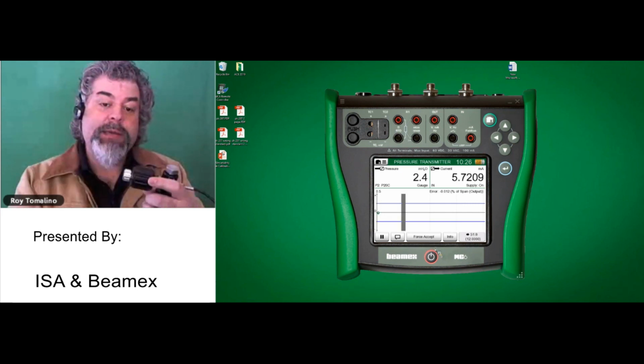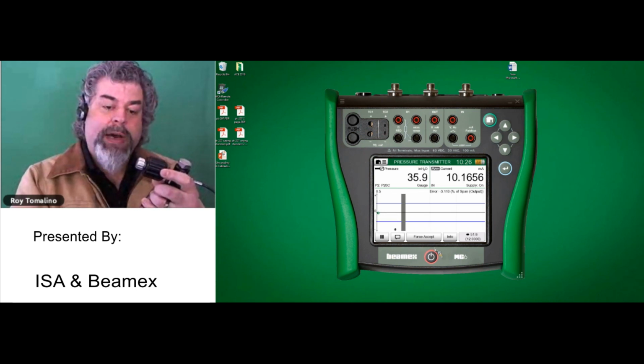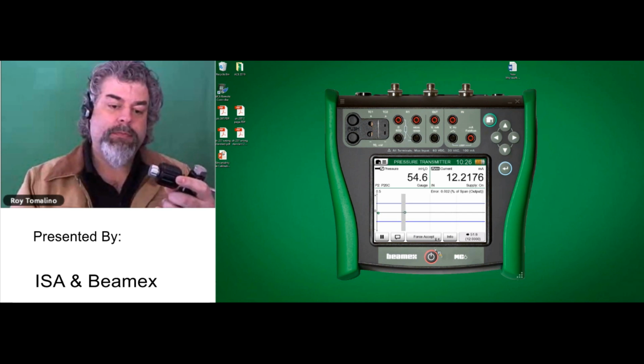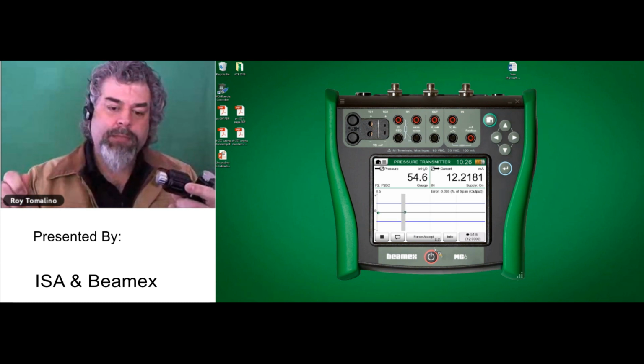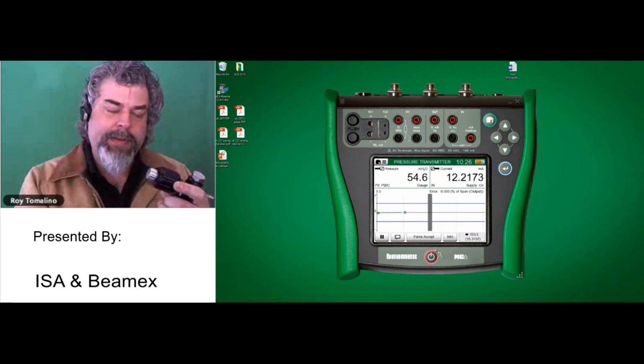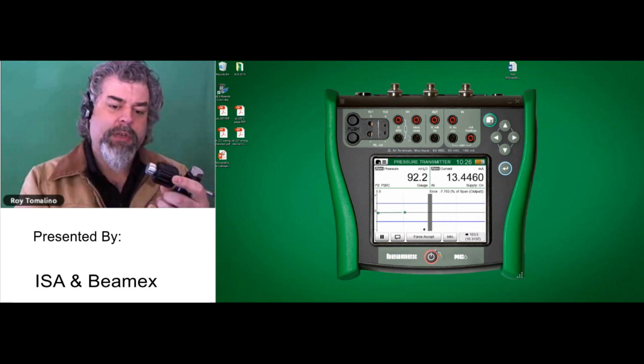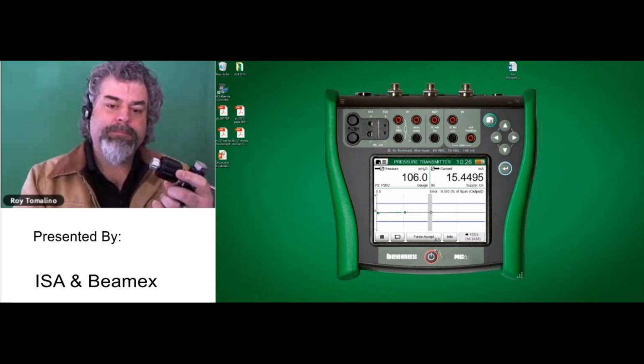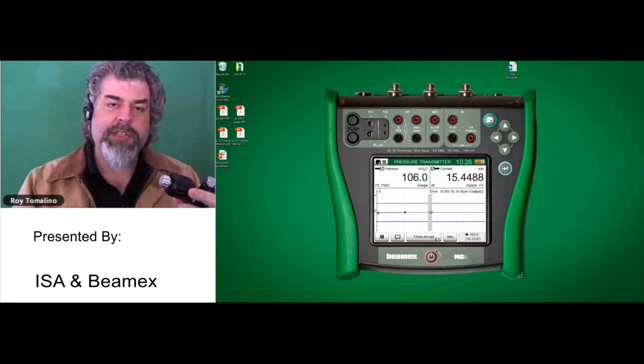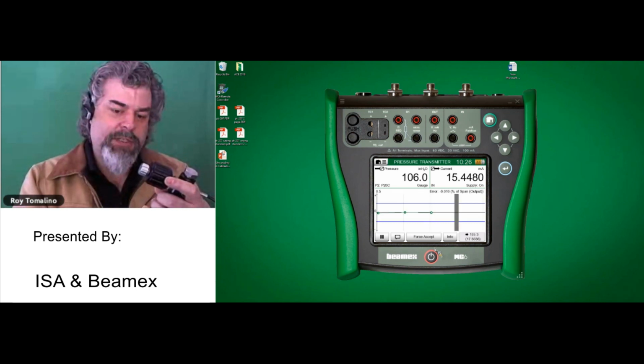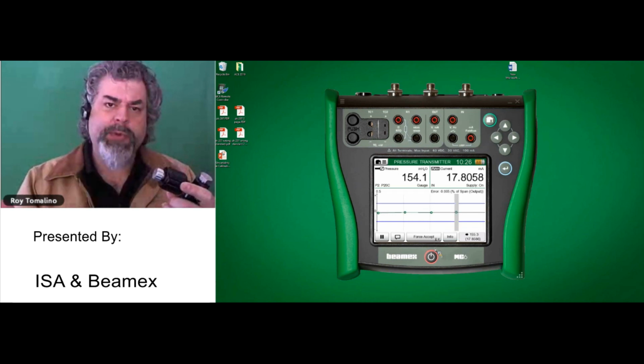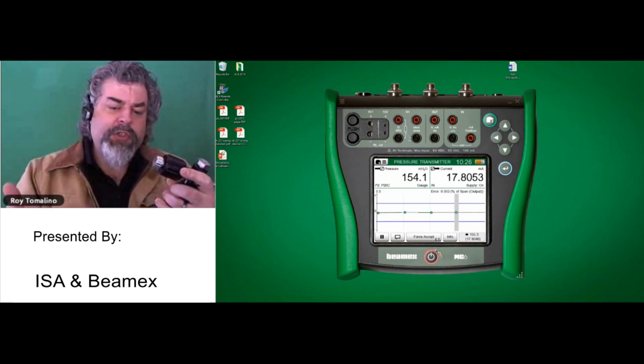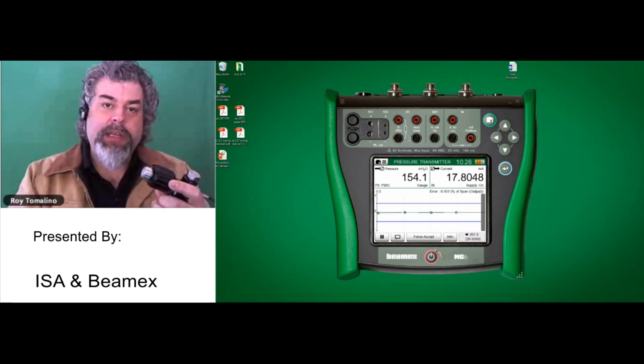And I have a 4-second delay in between each one. The bottom right is telling us where we're going next. The center line is 0 error. The blue lines represent our tolerance. I've got the tolerance set up as a quarter percent of span. This happens to be a critical transmitter in the process. So normally we'd be looking at about 0.5% of span, or maybe 1% if it's not critical. So this looks like it's absolutely right on the money.